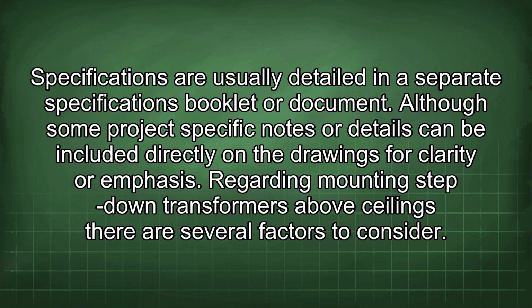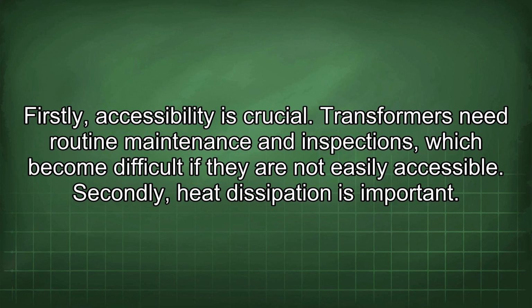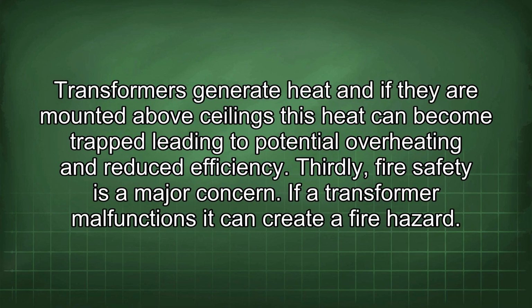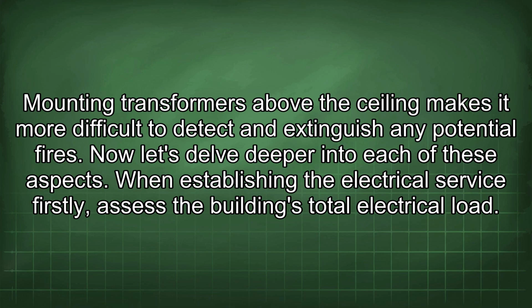Regarding mounting step-down transformers above ceilings, there are several factors to consider. Firstly, accessibility is crucial. Transformers need routine maintenance and inspections, which become difficult if they are not easily accessible. Secondly, heat dissipation is important. Transformers generate heat, and if they are mounted above ceilings, this heat can become trapped, leading to potential overheating and reduced efficiency. Thirdly, fire safety is a major concern. If a transformer malfunctions, it can create a fire hazard. Mounting transformers above the ceiling makes it more difficult to detect and extinguish any potential fires. Now let's delve deeper into each of these aspects.